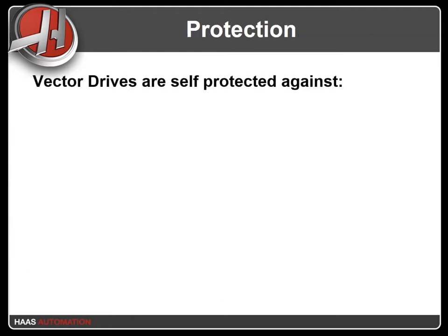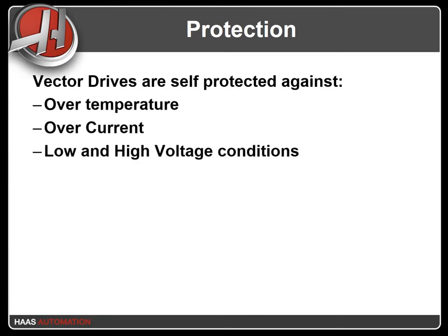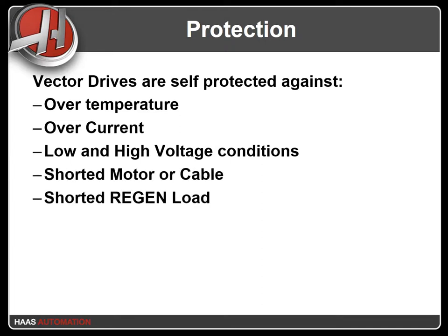Vector drives have protection circuits against abnormal conditions such as over-temperature, over-current, low and high voltage conditions, motor or cable short circuit, and shorted regen load. When one of these conditions is present, the Vector Drive will stop all outputs and will generate an alarm.